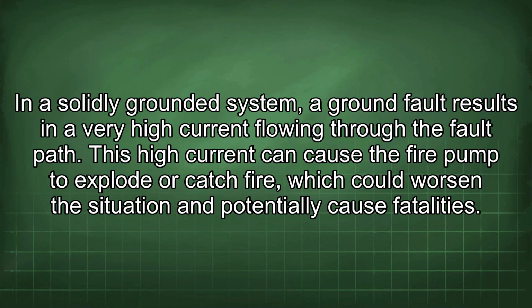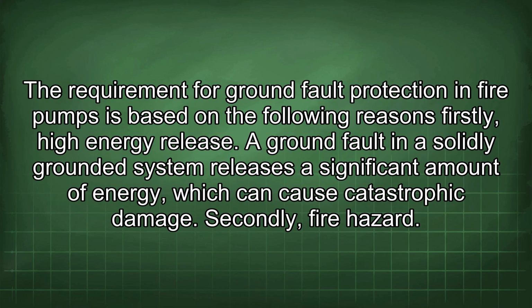In a solidly grounded system, a ground fault results in a very high current flowing through the fault path. This high current can cause the fire pump to explode or catch fire, which could worsen the situation and potentially cause fatalities. The requirement for ground fault protection in fire pumps is based on the following reasons.